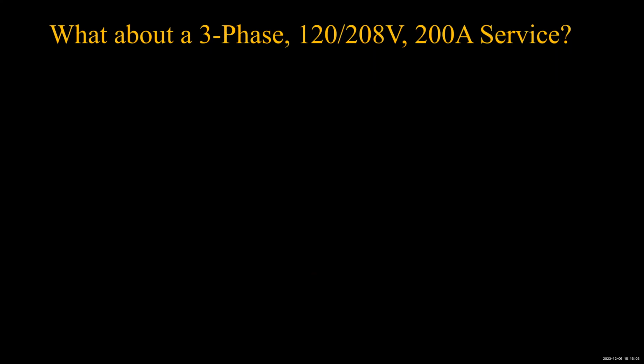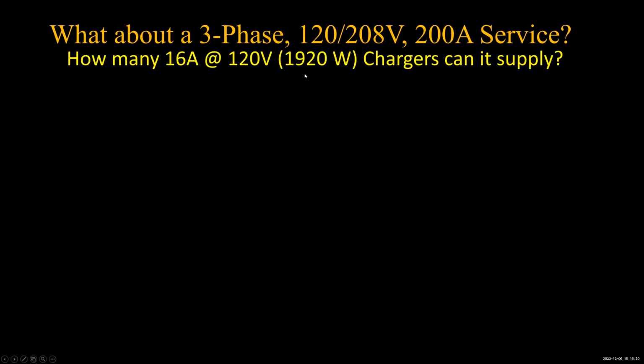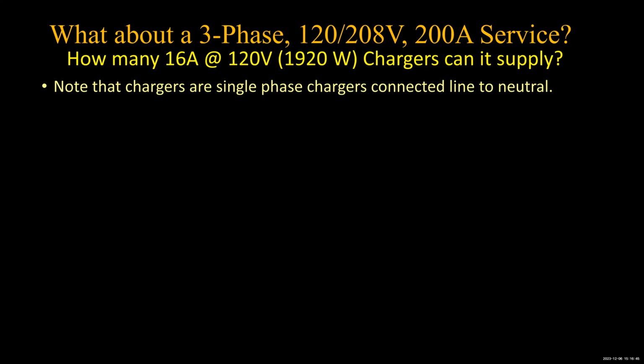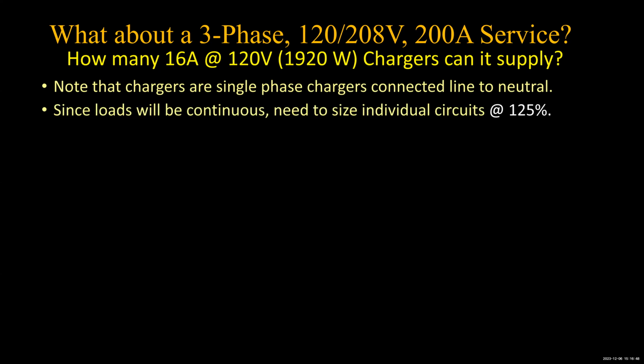What about three-phase? That's the fun part. Let's see, how are we doing on time? 45 minutes, all right. What about three-phase services? Because single phase is a piece of cake. Three-phase, little more complicated. Let's say we got a 200 amp, 120/208 three-phase service, and we want to connect 16 amp, in other words, 1920 watt single phase level 1 chargers. So that means we're going to go line to neutral on these. And we want to know how many we can connect. Well, first of all, they're single phase, so they're line to neutral. And the loads will be continuous, so we have to take the individual at 125%.